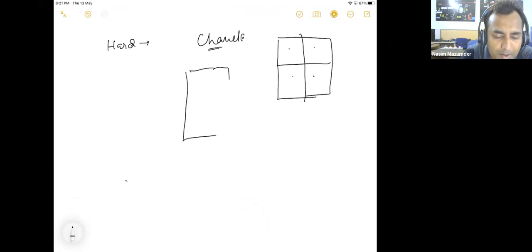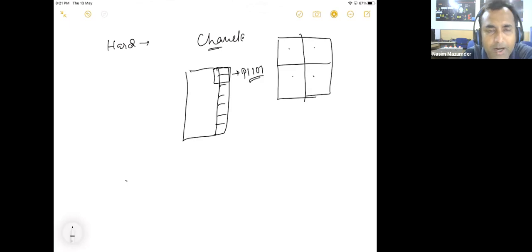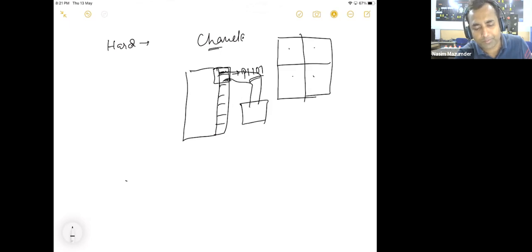This is my card. So I am assigning this particular channel as PI101. This is my hard tag, which is communicating directly with my field device. Soft tags are those tags which are communicating between your DCS or PLC and your SCADA.